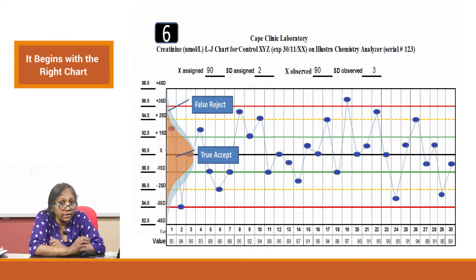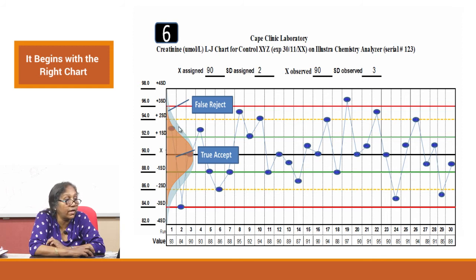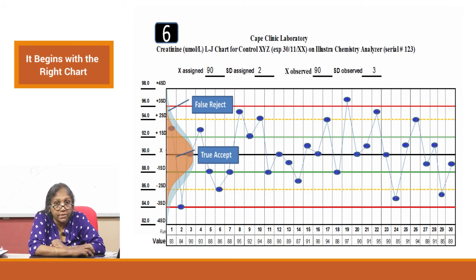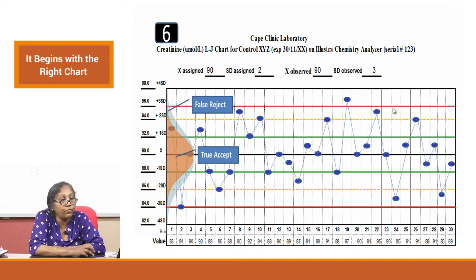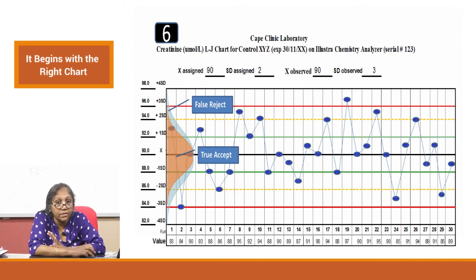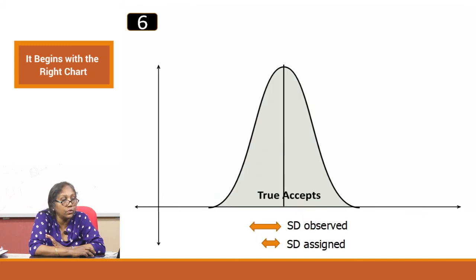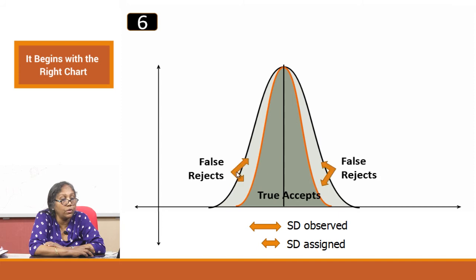Another case: mean is 90, assigned SD is 2, but your observed SD is larger than what you assigned. For no reason you will be rejecting runs. The true accept region is narrow and everything outside becomes a false reject because you assigned your SD too narrowly. You need to be sensible when assigning your SD — if assigned too narrowly, you are rejecting good runs that should have been within your 95 percent region.